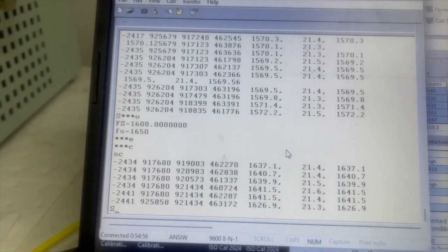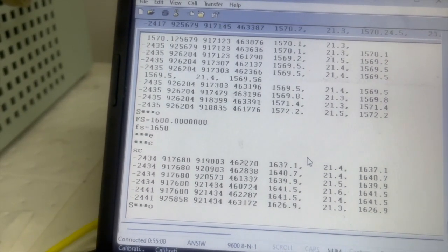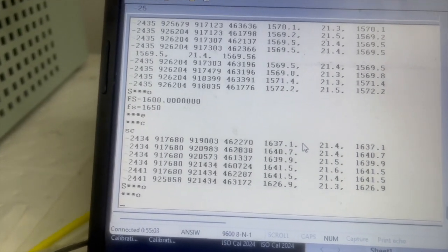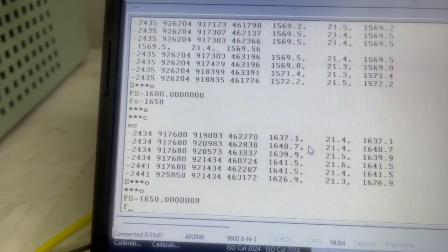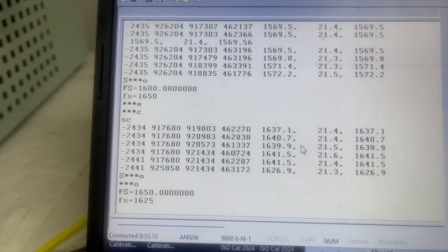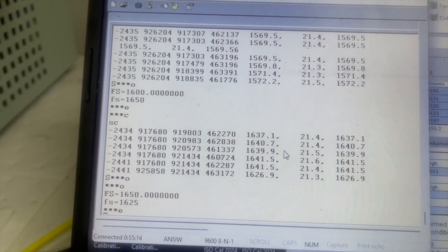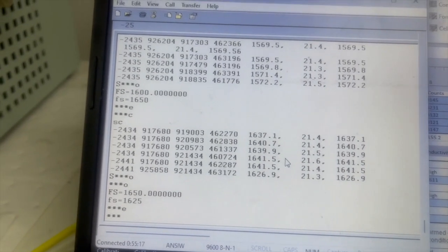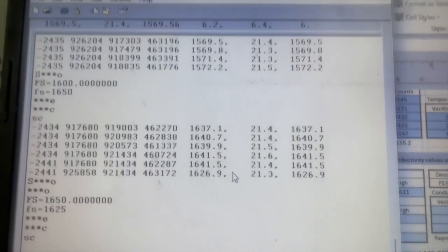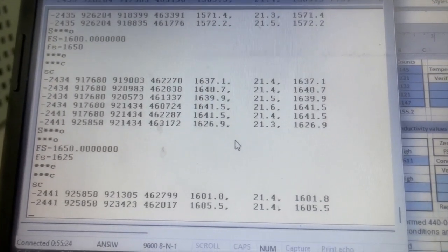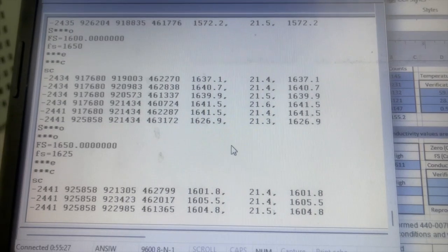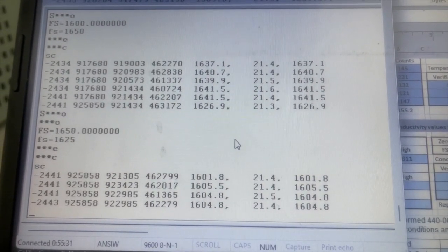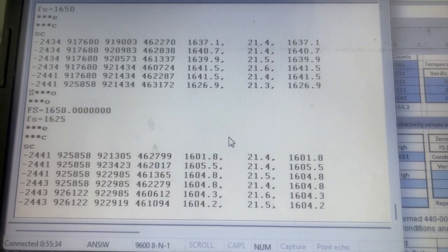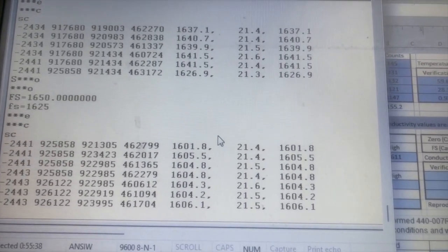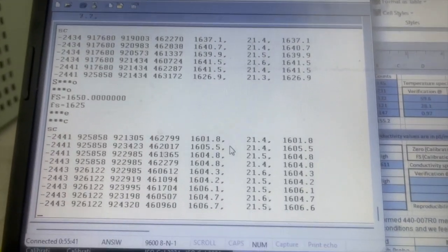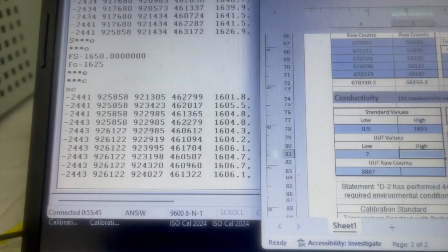So we're going to stop. We're going to go into open mode, which I already did. Go full scale equals 1625. So we do increments of 25 on the full scale. Save it. Back into cal mode and see how close we are. Looking for 1611-ish, and we're getting 1604, which is very close at that scale. 1606. So that's pretty close. It's as close as you're ever going to get.